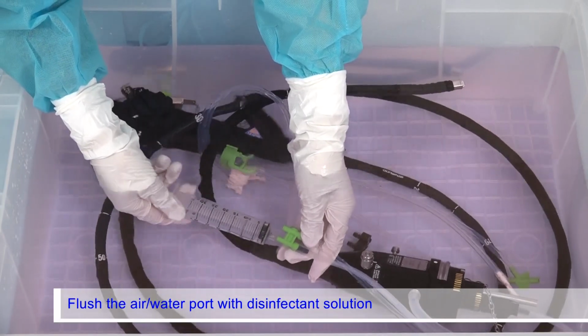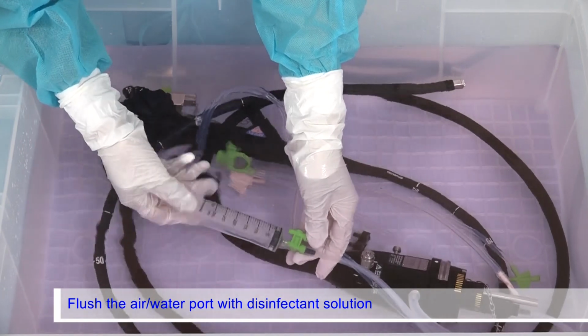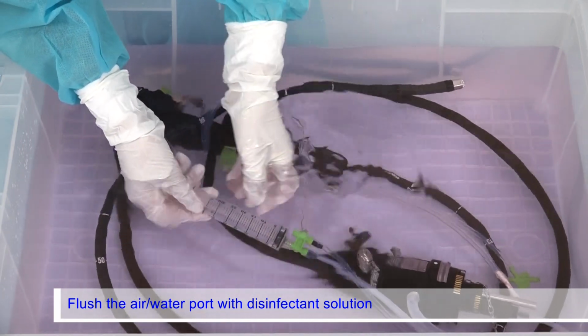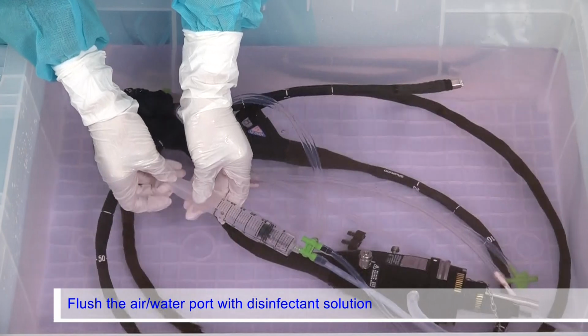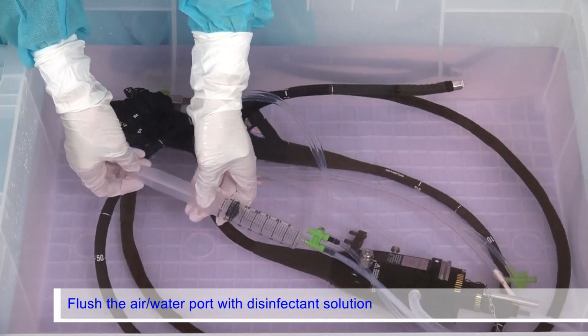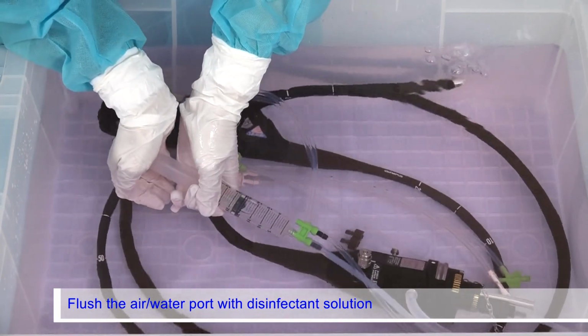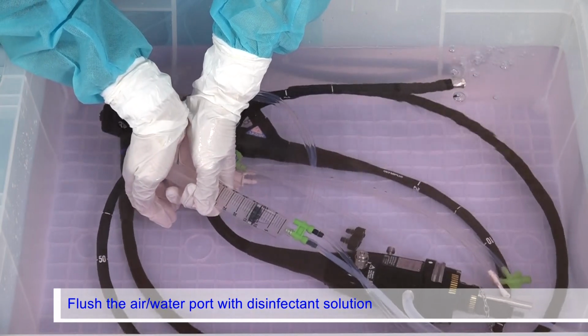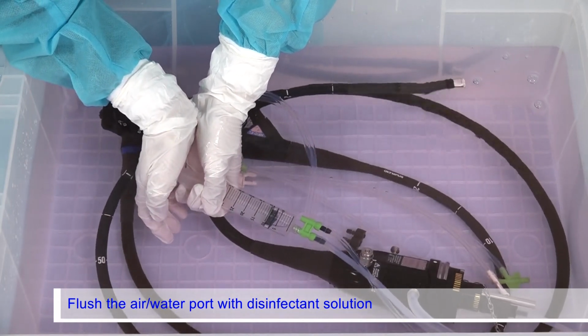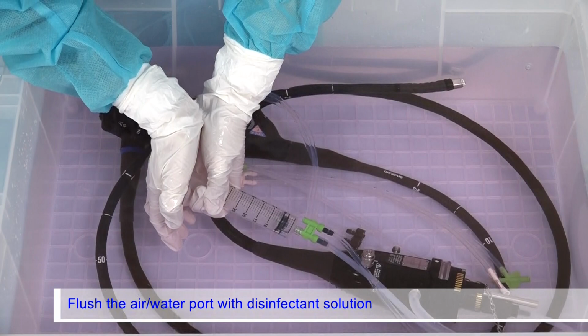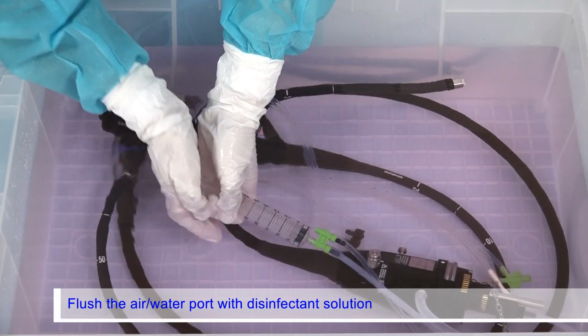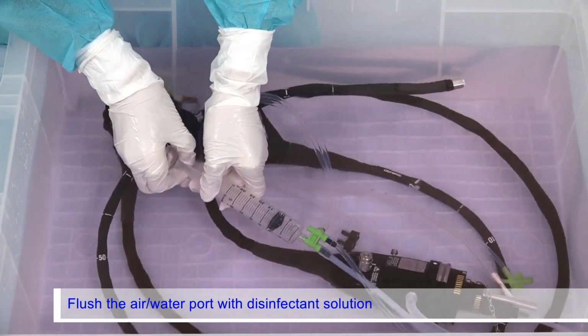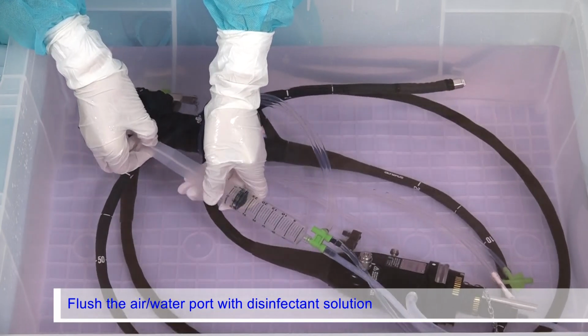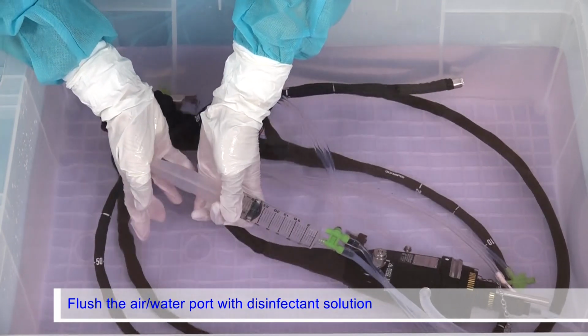Move the syringe to the air-water channel port of the injection tube. While immersing the syringe completely in the disinfectant solution, slowly pull the syringe plunger to fill the syringe with the disinfectant solution. Then, forcefully push in the plunger to flush the air-water channel with 30 milliliters of the disinfectant solution. Repeat the step 5 more times.